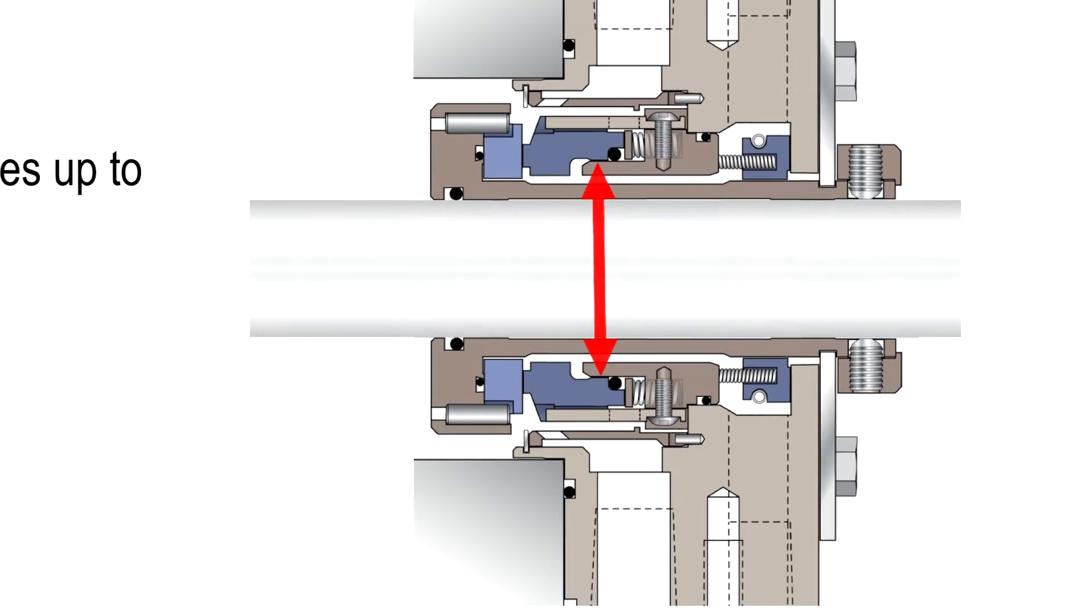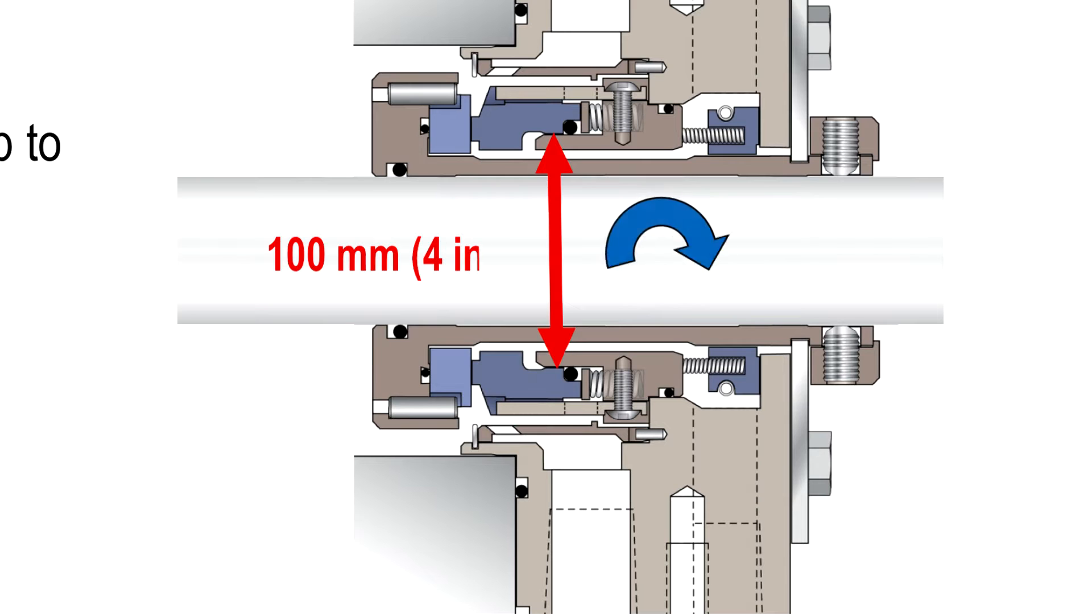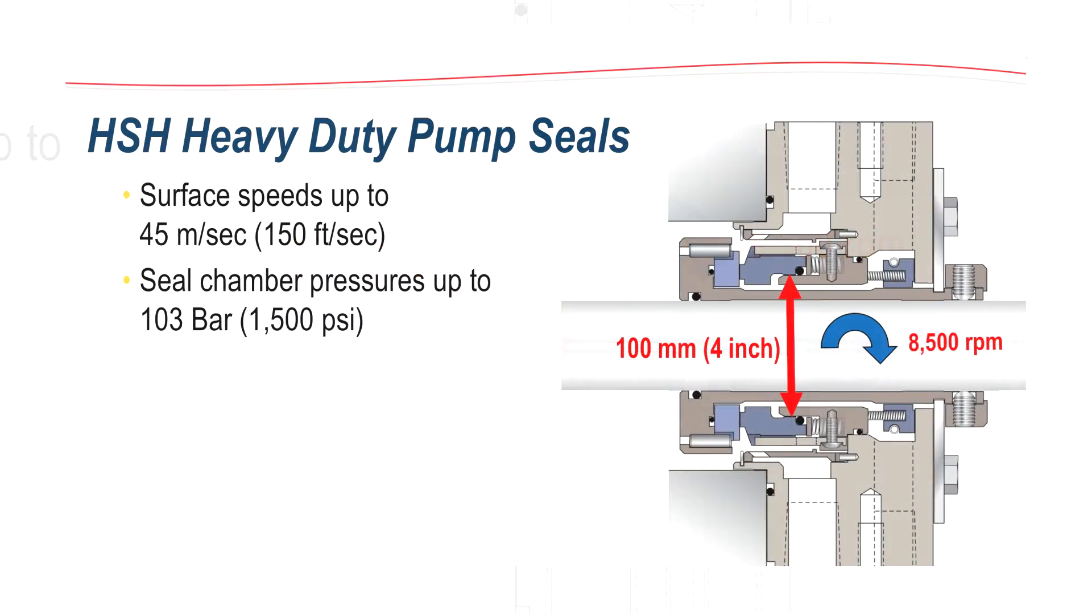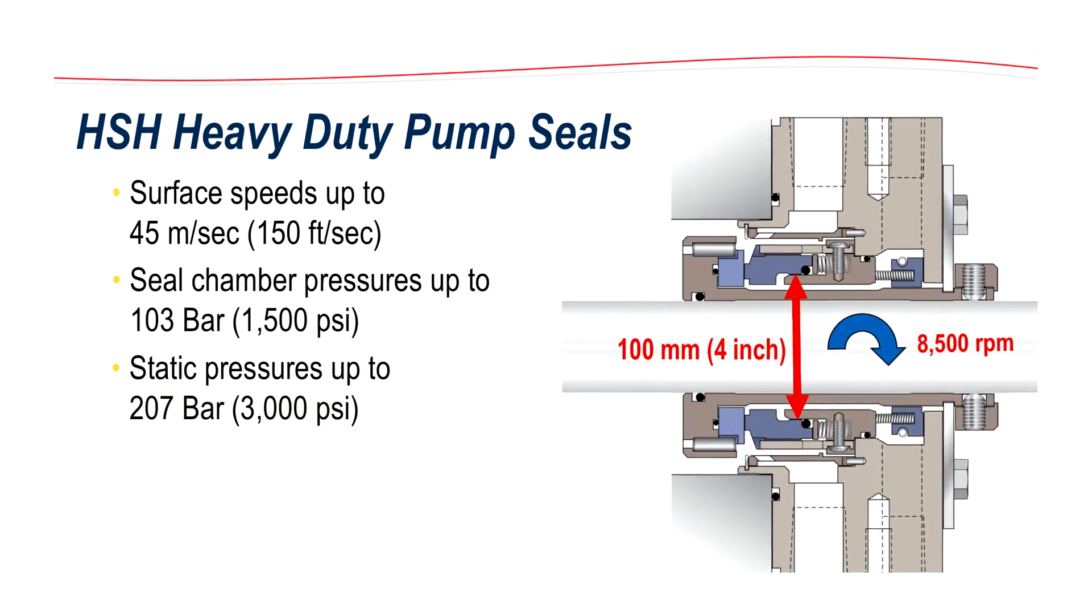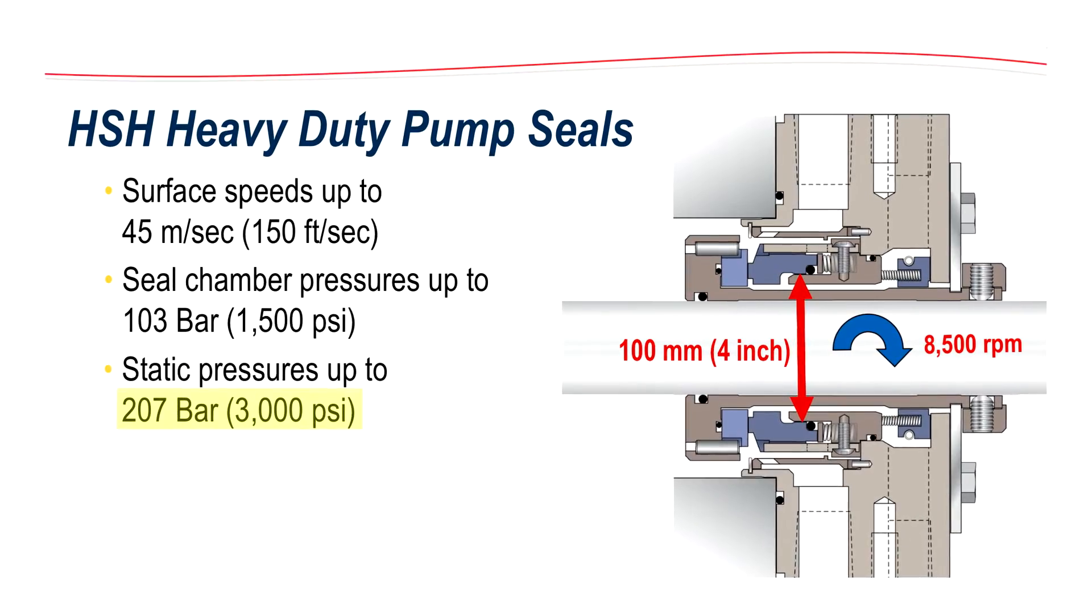For example, a 100 millimeter or 4 inch seal size could be used at speeds up to 8,500 RPM. The seal is so robustly built that it could handle static pressures up to 207 bar, 3000 PSI.